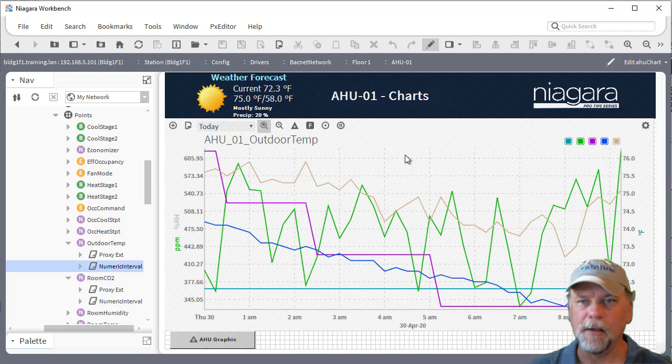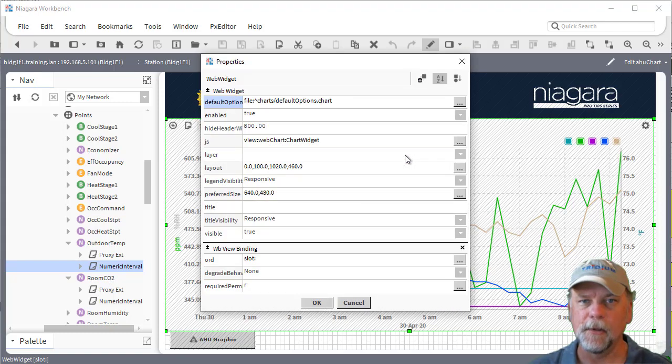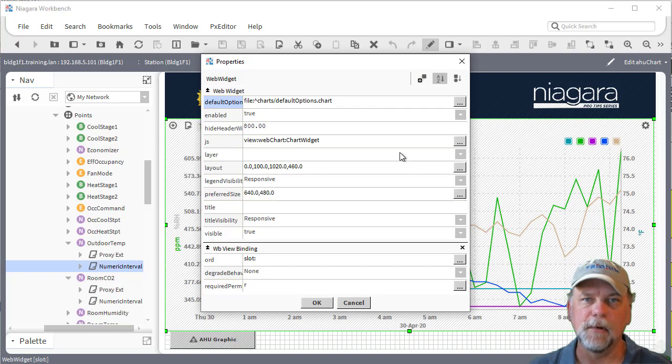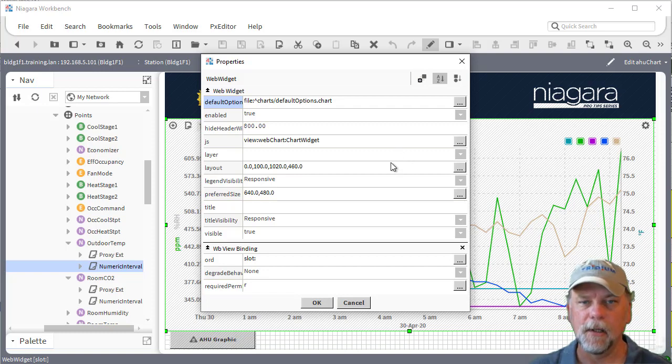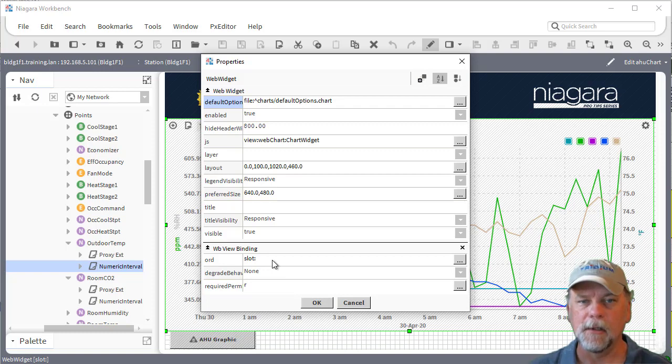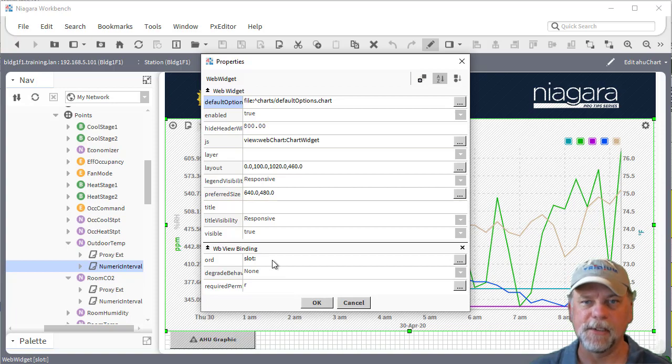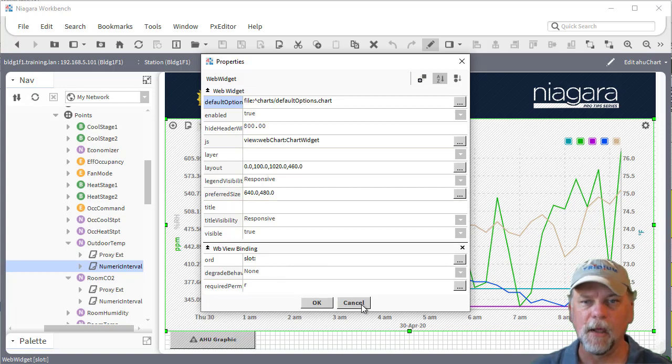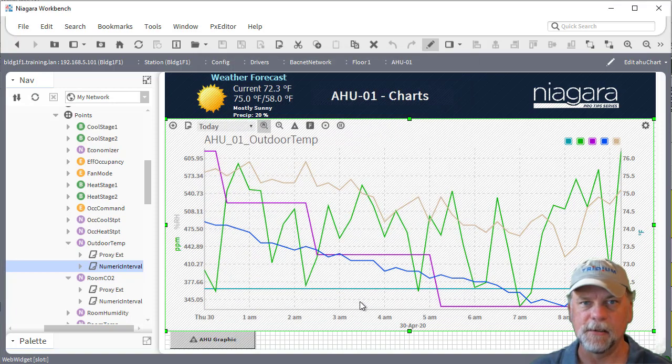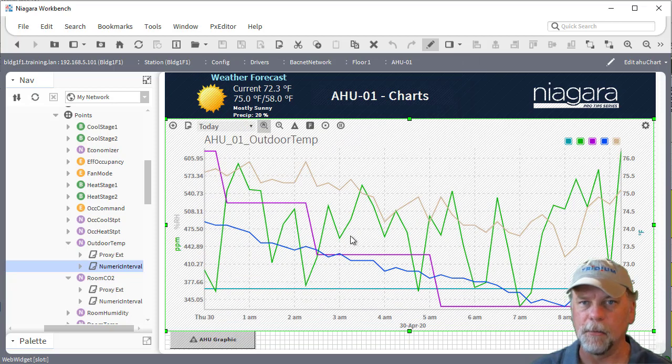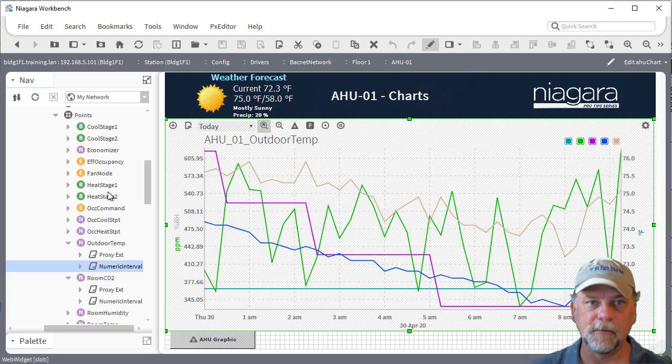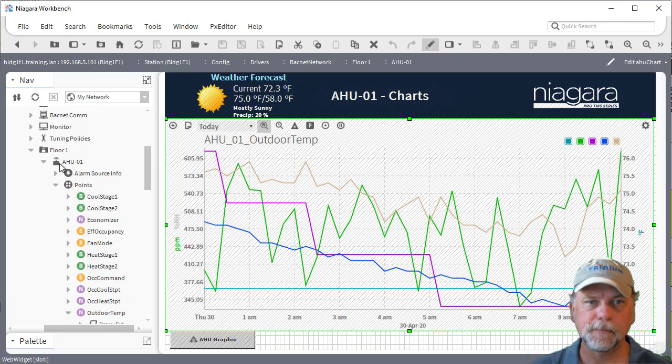And in the PX view I have a web widget with the web chart and it has the general kind of slot colon relative ORD which is pointing to the device and then it's mapping in up to the first 10 histories from that device. We've already talked about some other ways to do multiple WBV bindings and that sort of thing as well.